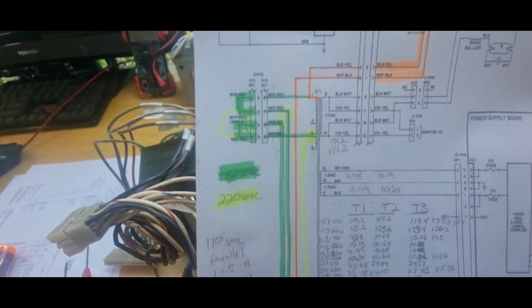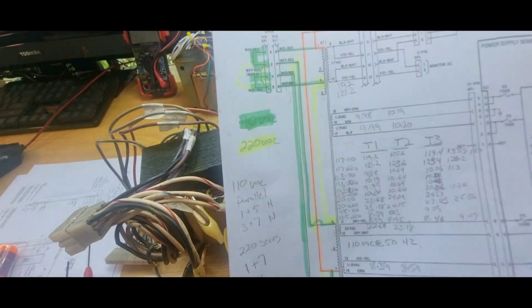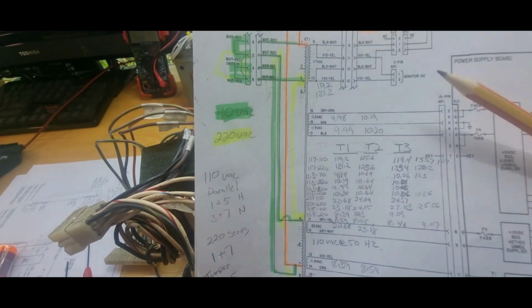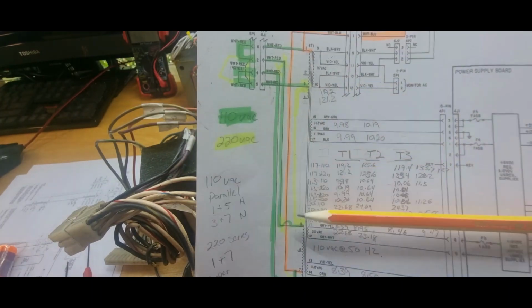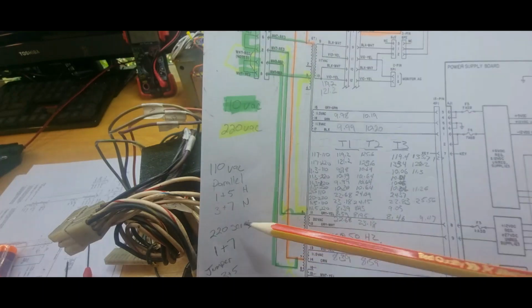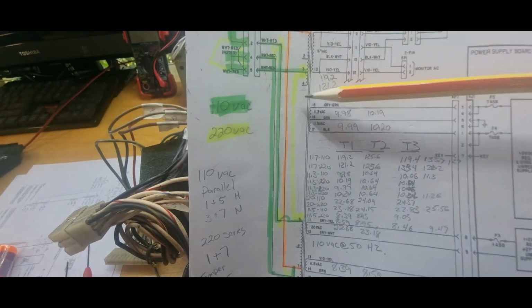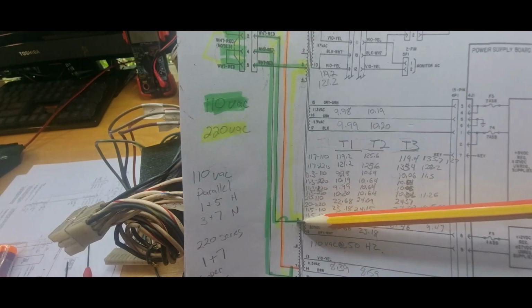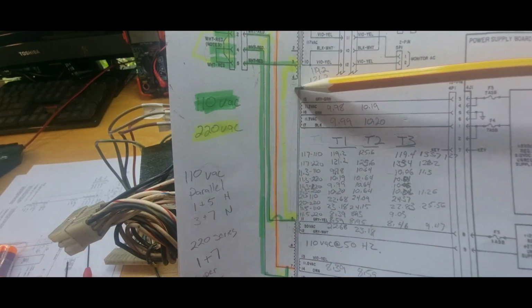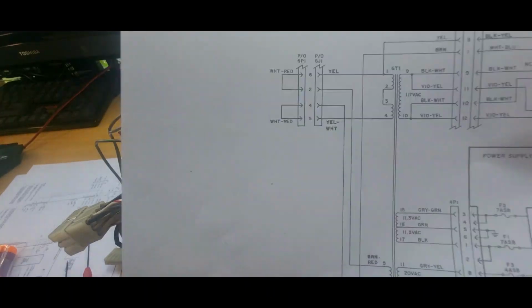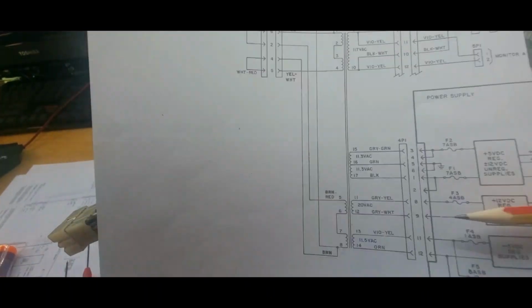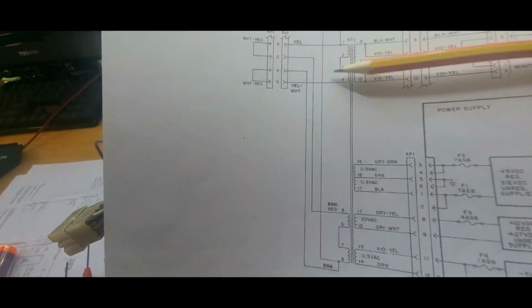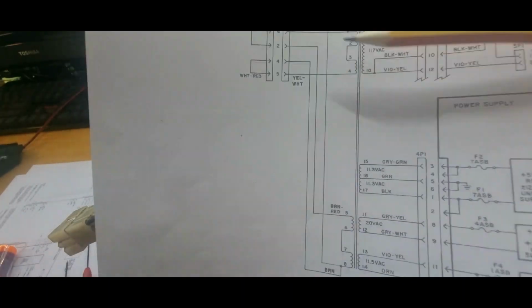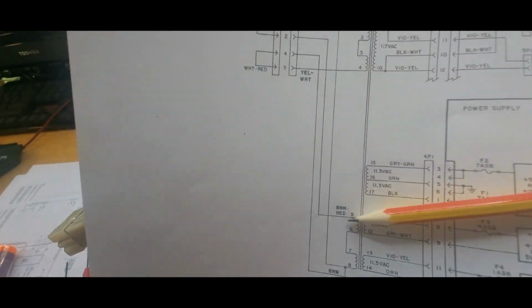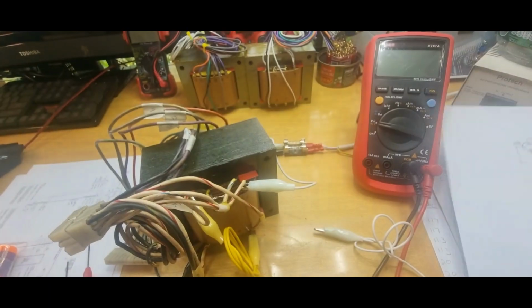Just looking at it simply, making sure I don't touch anything. For 220, since we're running it in series, visually you can see we have two windings, and we're just going to bridge tap 5 to tap 4. Coming over to the proper print makes it a little easier to see. You have two windings wired parallel, but for series we're just going to connect pin 4, tap 4, and tap 5, which we've done.